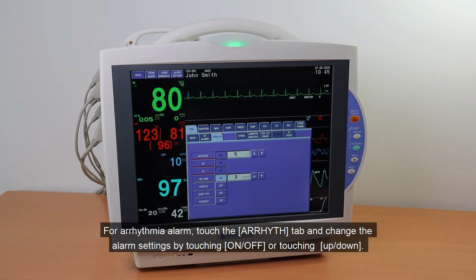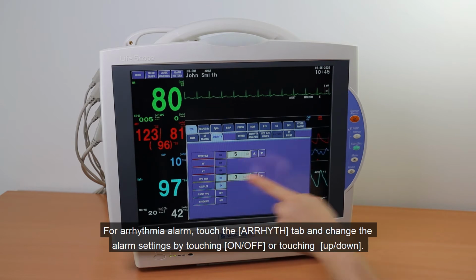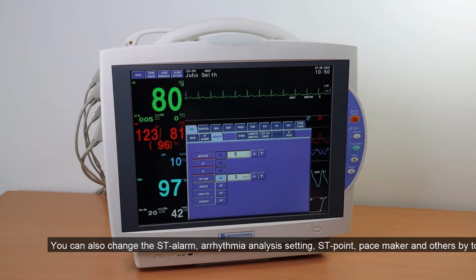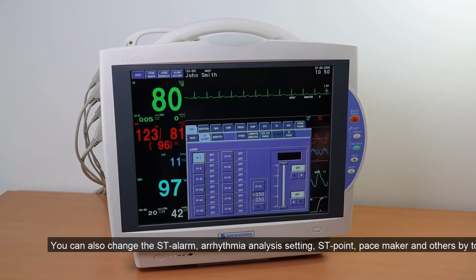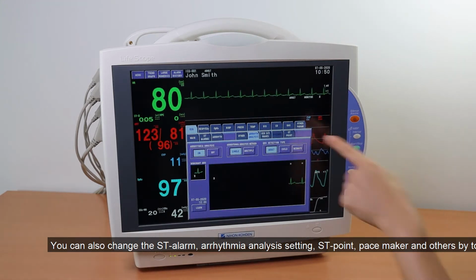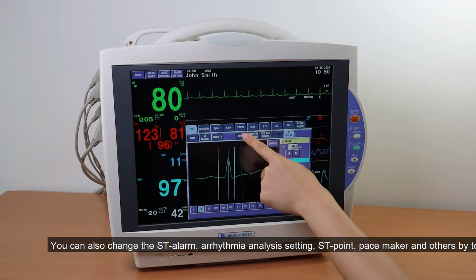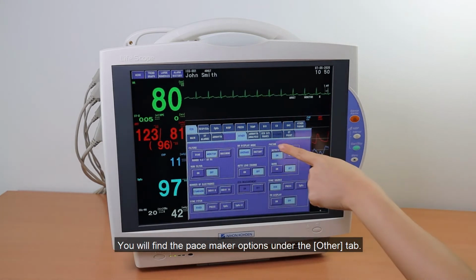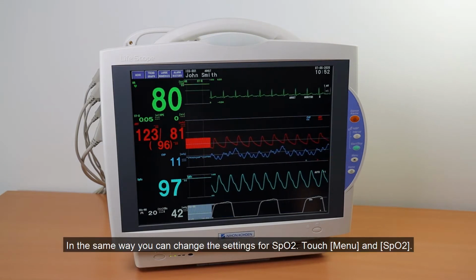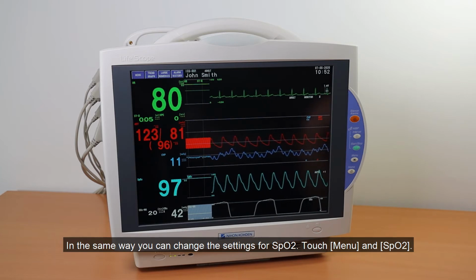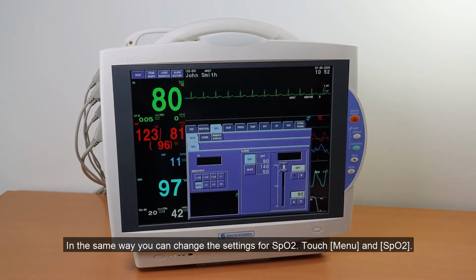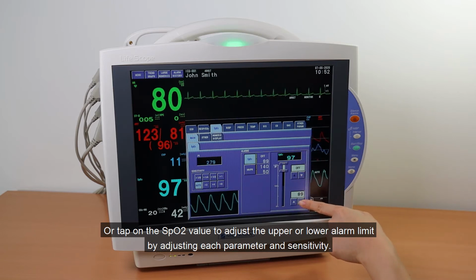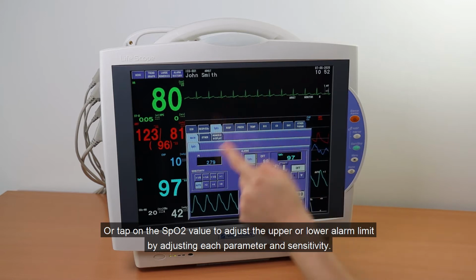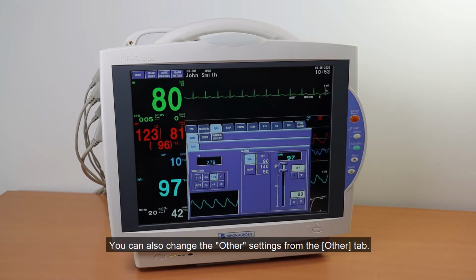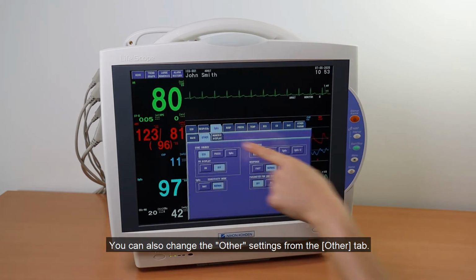For arrhythmia alarm, touch the Arrhythmia tab and change the alarm settings by touching On/Off or touching up and down. You can also change the ST alarm, arrhythmia analysis setting, ST point, pacemaker, and others by touching the tabs. You will find pacemaker options under the Other tab. In the same way, you can change the settings for SpO2. Touch Menu and SpO2, or tap on the SpO2 value to adjust the upper or lower alarm limit by adjusting each parameter and sensitivity. You can also change the Other settings from the Other tab.